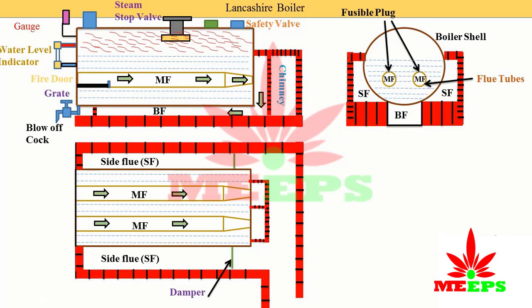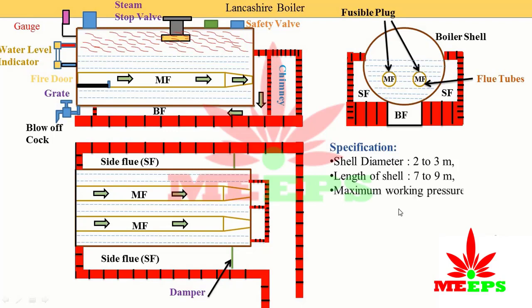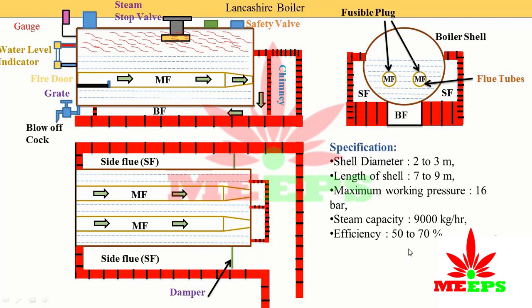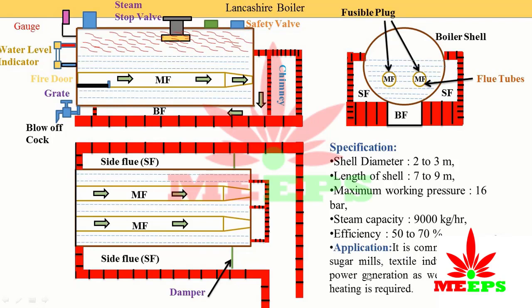Specifications of the Lancashire boiler: shell diameter is 2 to 3 meters; length of shell is 7 to 9 meters; maximum working pressure is 16 bar; steam capacity is 9000 kg per hour; and efficiency is 50 to 70 percent. It is commonly used in sugar mills and textile industries where both power generation and process heating are required.